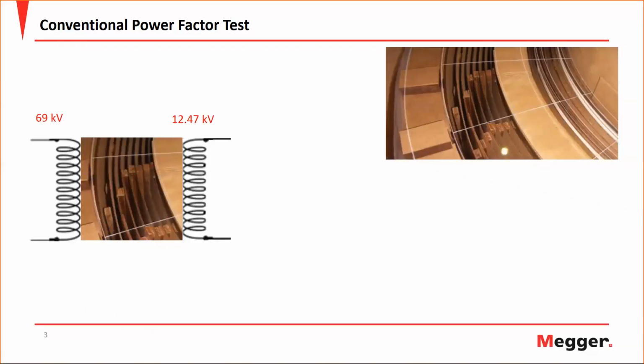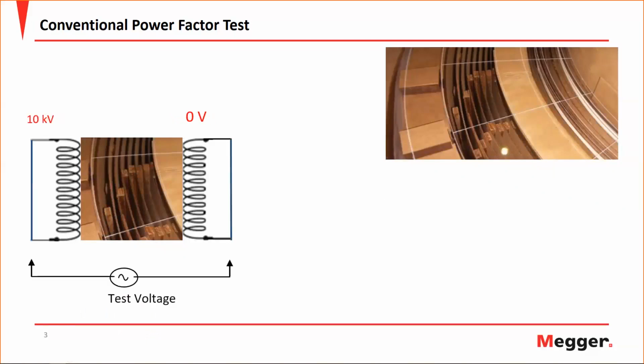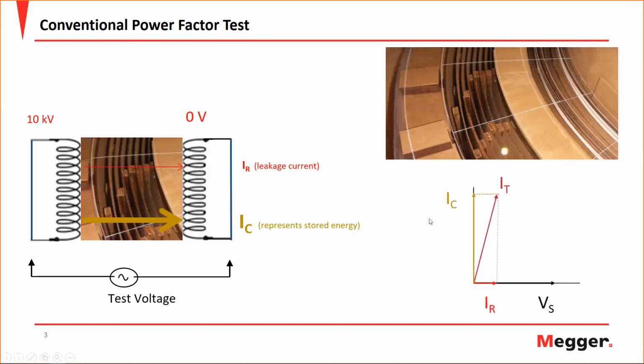The traditional power factor that we're doing is taking a winding, let's say we have a transformer that's 69 kV to 12.47. We are then going to short the windings together, apply some voltage to the primary winding, and then measure some current that comes out on the other side. I know this is for a transformer, but the same concept applies to testing a bushing, except that total current is actually broken into a few different sections, one being the leakage current, the other being the capacitive current, and everybody has seen this sort of vector diagram here, and this is what we use to calculate either power factor or tan delta.